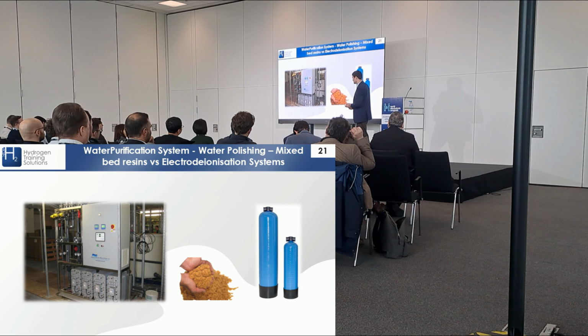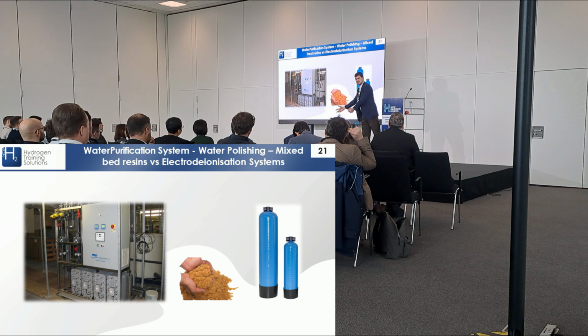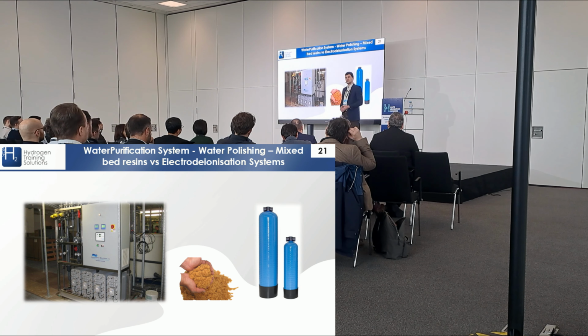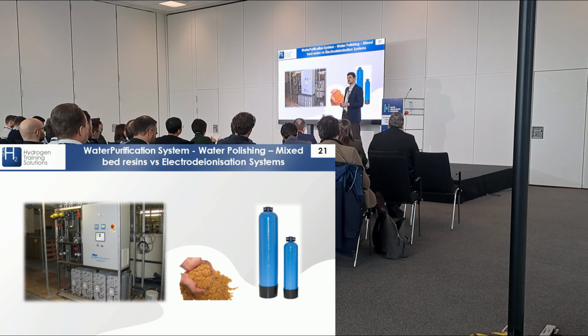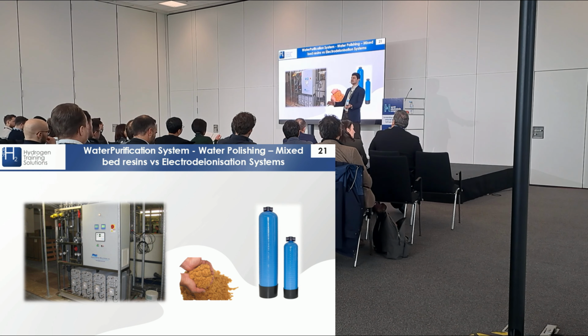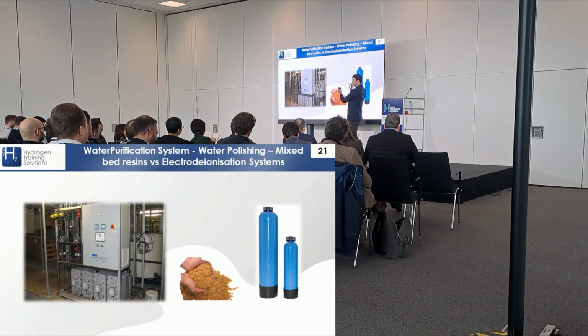Actually, after the water is in contact with this catalyst, out of these vessels the water comes out at around 0.1, sometimes even 0.09 microsiemens per centimeter, and the theoretical lowest you can get to is 0.056 microsiemens per centimeter. So you're able to get very close to the theoretical minimum conductivity of water.